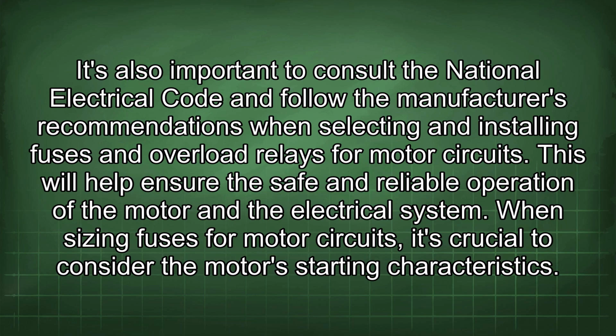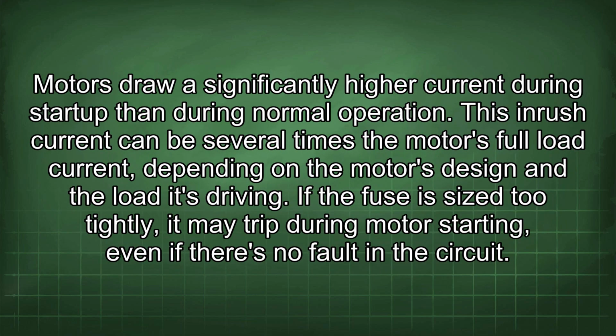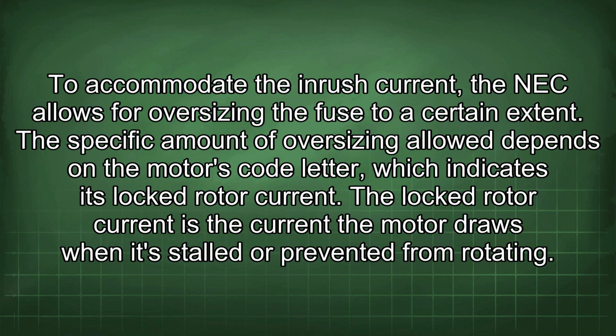When sizing fuses for motor circuits, it's crucial to consider the motor's starting characteristics. Motors draw a significantly higher current during startup than during normal operation. This inrush current can be several times the motor's full load current, depending on the motor's design and the load it's driving. If the fuse is sized too tightly, it may trip during motor starting, even if there's no fault in the circuit. To accommodate the inrush current, the NEC allows for oversizing the fuse to a certain extent.